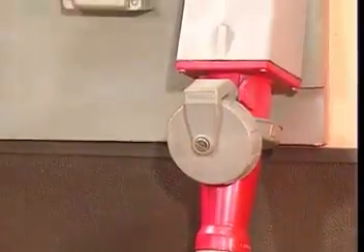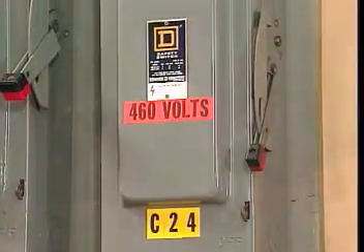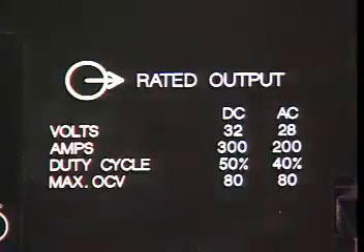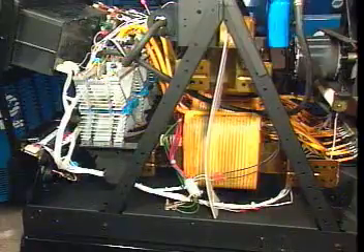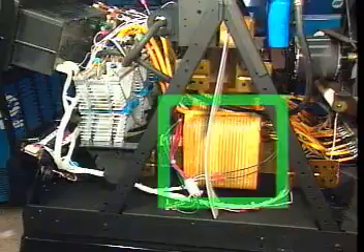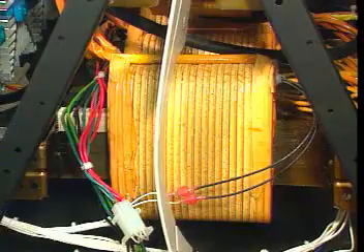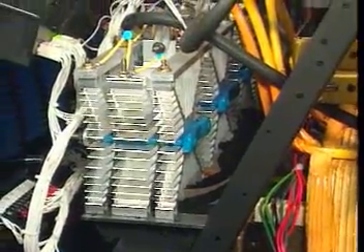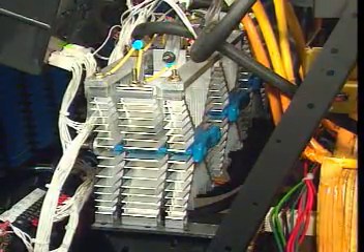When a welding machine uses commercially available electric power, it has to change the high voltage, low amperage alternating current from the utility's power lines to a low voltage, high amperage AC or DC welding current. While electric motors were once used for this conversion, modern welding machines use transformers to produce AC welding current. To also produce a DC welding current, the transformer's output is connected to a rectifier. A rectifier is a device that changes alternating current to direct current.